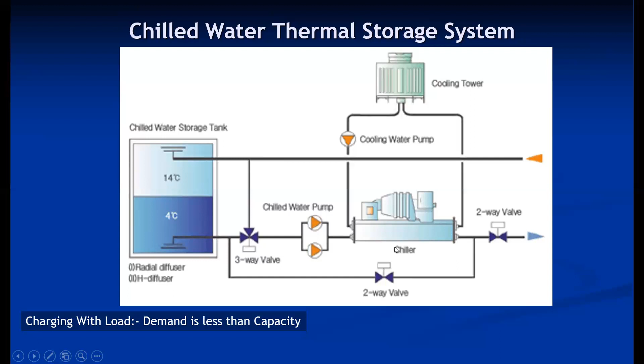Suppose the chiller capacity is 100 kilowatt, and the demand is 75 kilowatt, but the chiller is continuously working at 100 kilowatt. So what will happen in this case? The chilled water required for 75 kilowatt is supplied through the supply line, and the remaining chilled water, about 25 kilowatt capacity, is stored in the storage tank through this two-way valve. This mode is called charging with load. So the chiller handles the load as well as charges the storage tank.